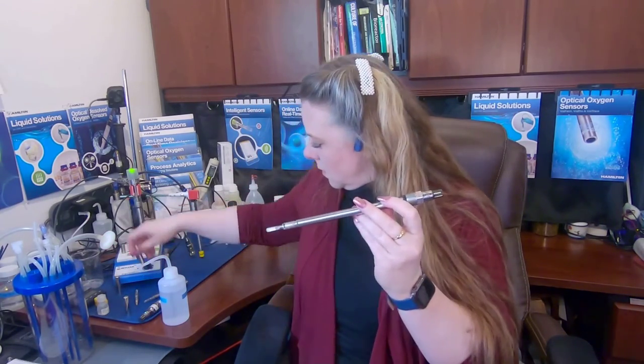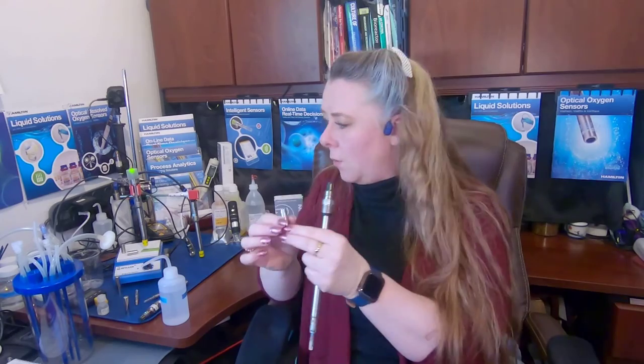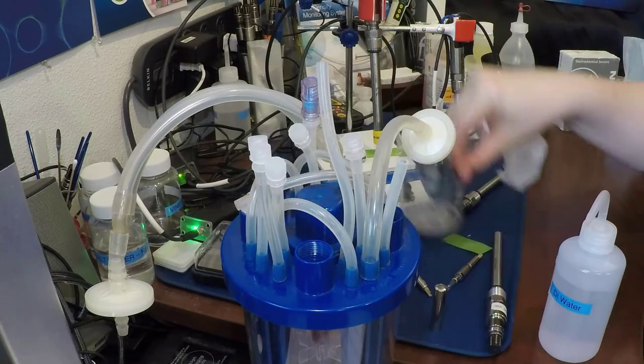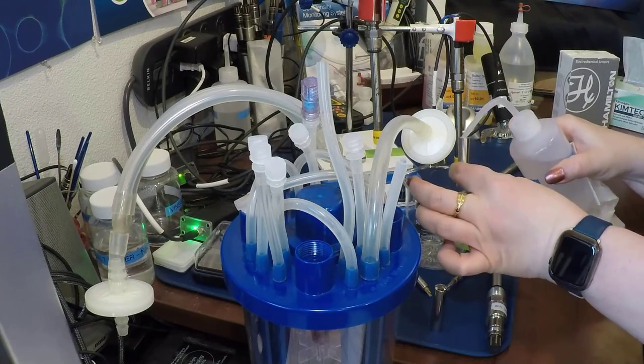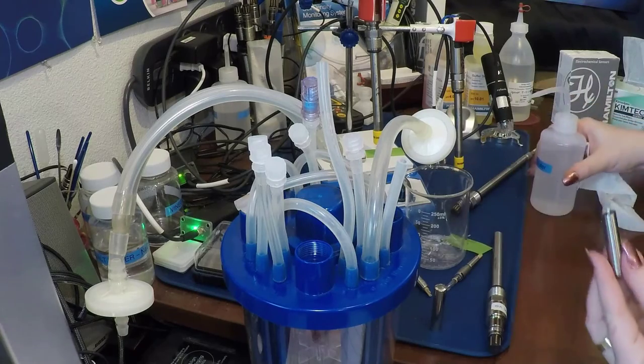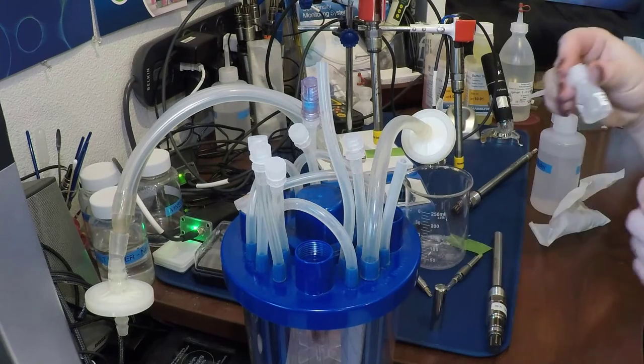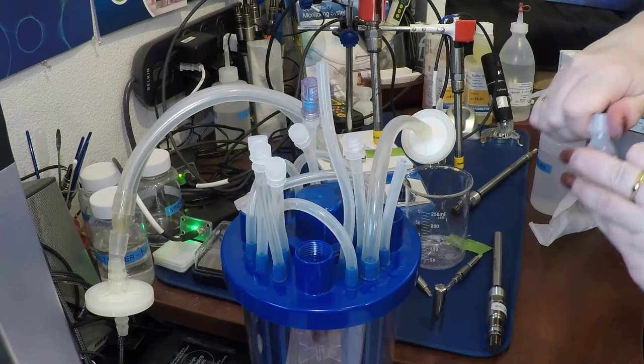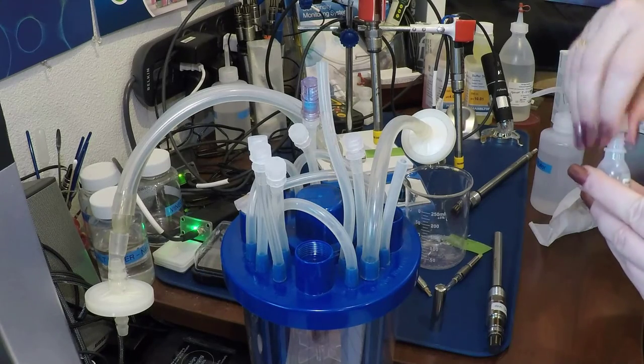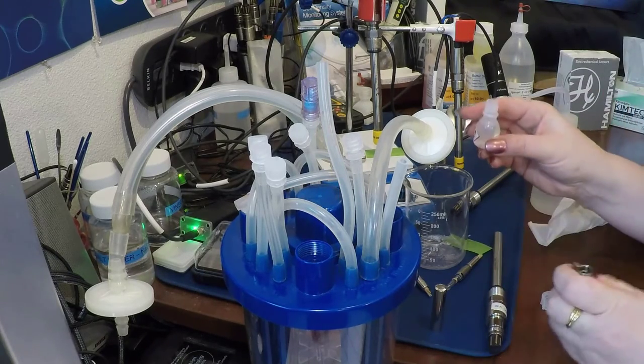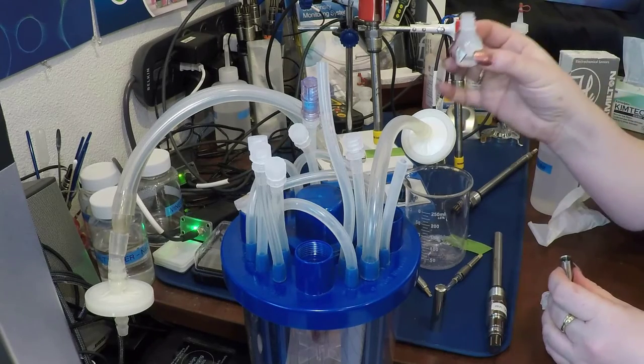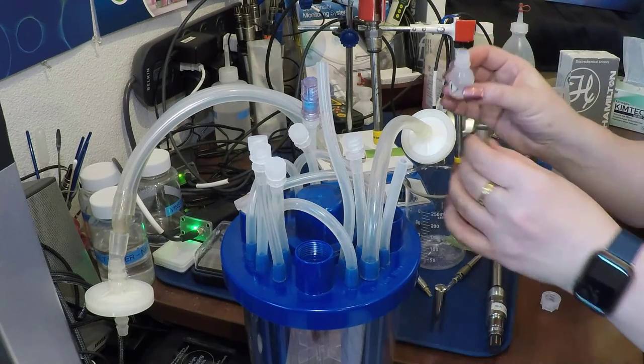Okay. So that is what you want to do every single run. You had electrolyte left in here, and you want to dump that out. You want to rinse this container out so that you have nothing in there that shouldn't be. And then you're going to put in the correct electrolyte, and every manufacturer has a specific electrolyte for their polarographic probes. Always use the electrolyte from the manufacturer of the probe you're using, because it was all optimized together.